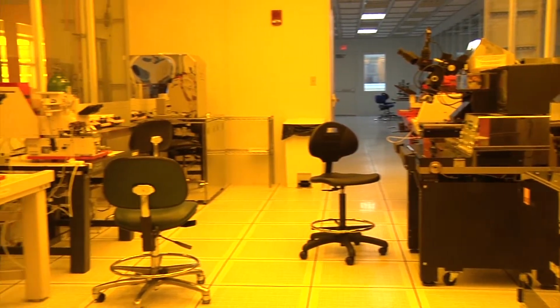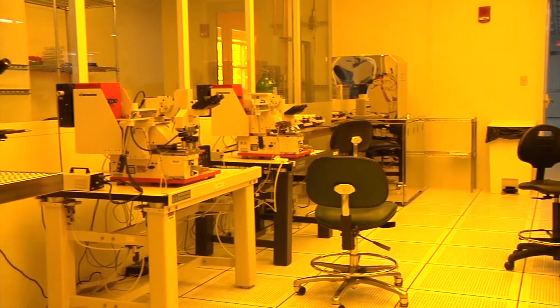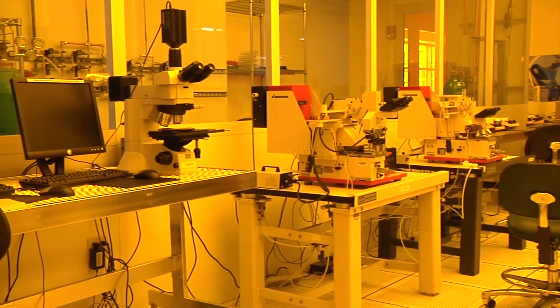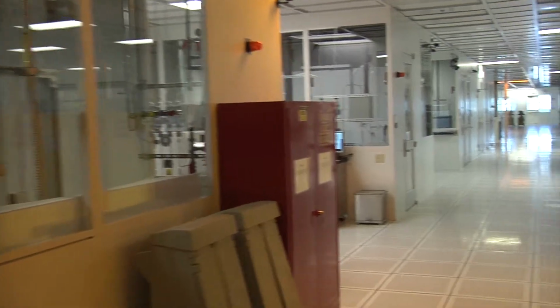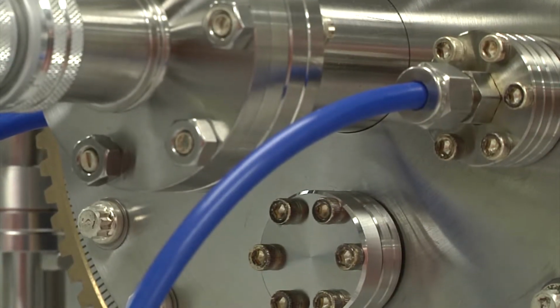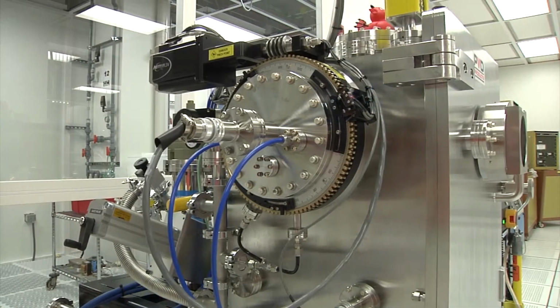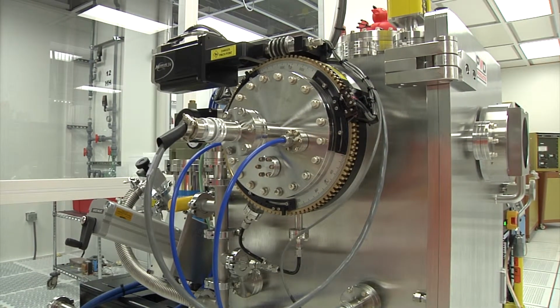There are, again, two good reasons for using a bay chase design in a research clean room such as ours. One of those reasons is it makes the facility more green. It cuts down on your air handling costs very significantly because you only have to treat the air that's going into the bays, not the chases. And that makes up about half the clean room. So you cut your utility cost essentially in half by just treating that air that's going through the bays.